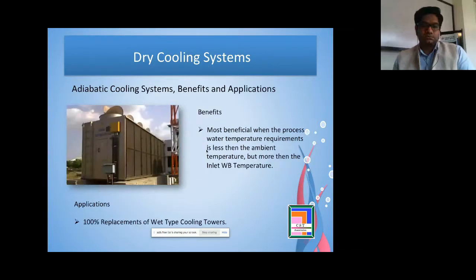So, adiabatic cooling system benefits and application. Most beneficial is when the process water temperature is less than the ambient temperature. So typically that is our case for the thermal power stations, where we need to have 32, 33 degrees centigrade of the water outlet temperature from the cooling tower. So this is basically an application of 100% replacement of wet type cooling tower, but saving a great amount of water.